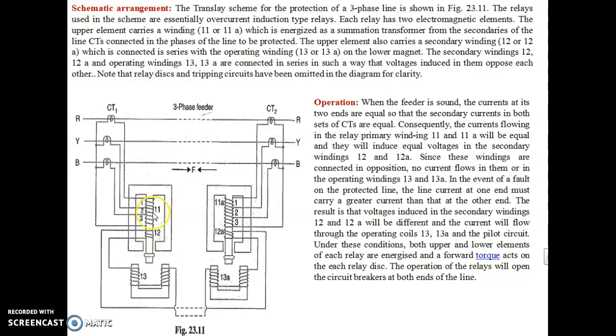The primary is denoted as 11, here 11A. The second winding here is 12 and here 12A, which is connected in series with the operating winding, 13 and 13A. See, the 12 and 12A secondary windings are connected to 13 and 13A, that is the operating winding. The U-shaped operating winding is connected in series; these two are connected in series. Okay. See, note that the relay disc and tripping circuit have been omitted in the diagram for clarity, that will be shown in the next slide, right?